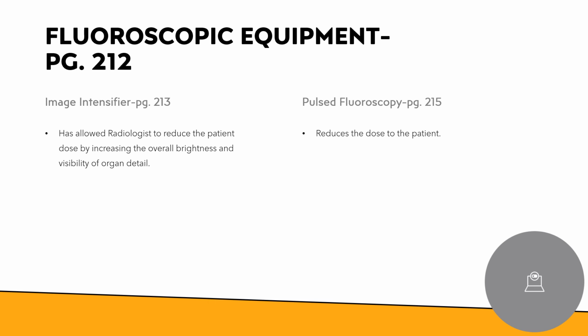When we look at fluoroscopic equipment, that's going to be on page 212. Starting there, your image intensifier allows the radiologist to reduce the patient dose by increasing the overall brightness and the visibility of the organ detail. And then the pulse fluoro replaces the real-time fluoro. The pulse fluoro is intermittent live exposure, and that helps to reduce the dose to the patient while still allowing the operator to be able to see some sort of live or real-time radiation images.